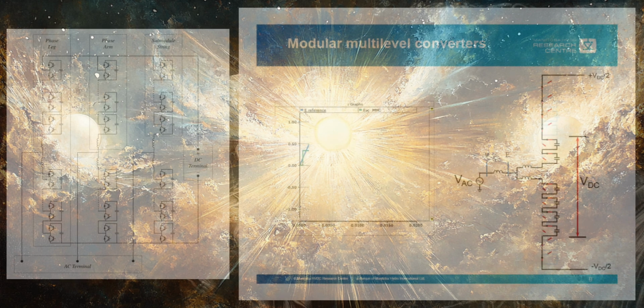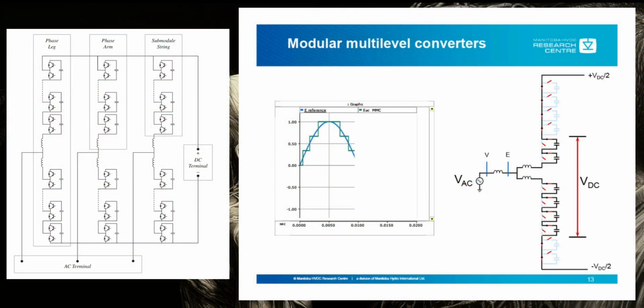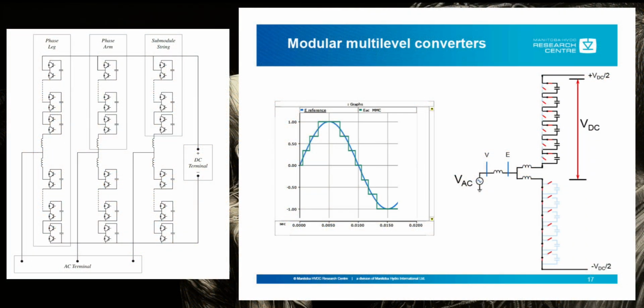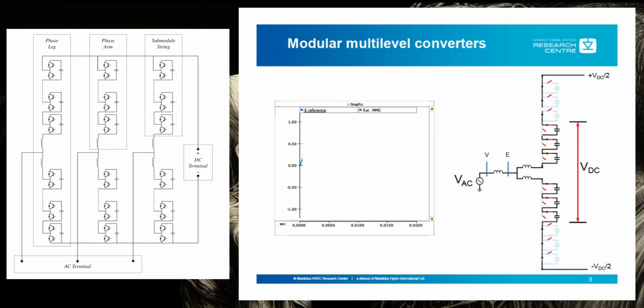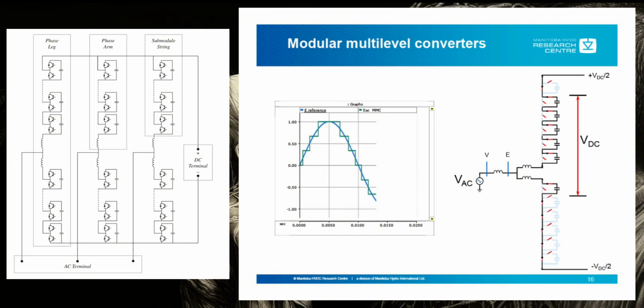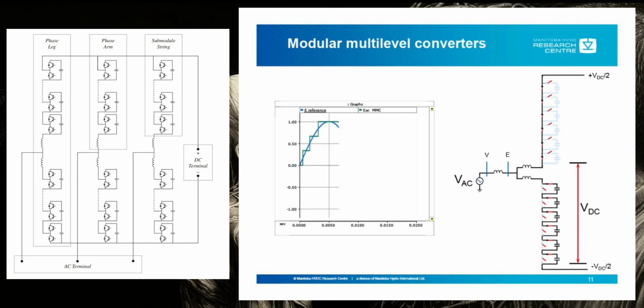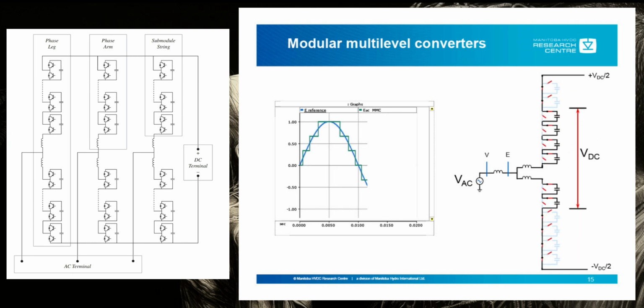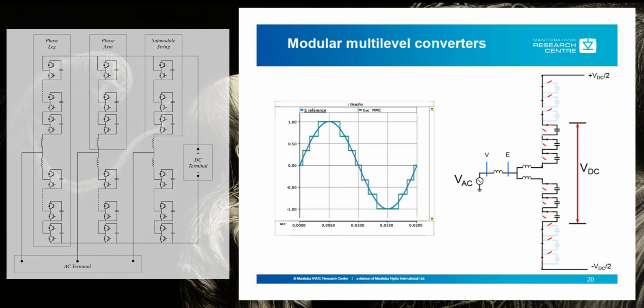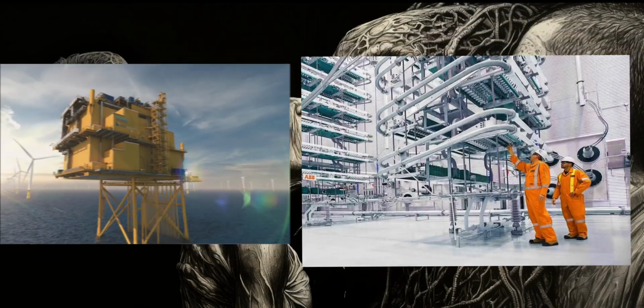The MMC is different, however. By having large strings of IGBT submodules, the output AC signal for an inverter will already resemble a strong sinusoidal waveform. As such, there will be significantly less harmonics. This dramatically increases the reliability of the converter, which is important for bulk power transmission.